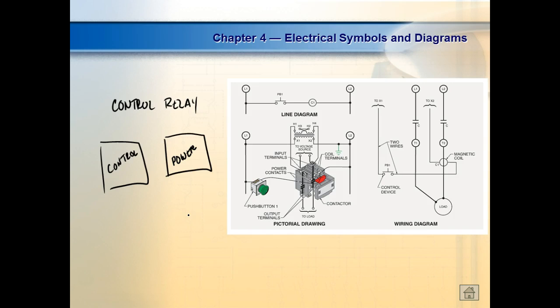So we have a control relay. A control relay, all its contacts are going to be in the what circuit? They're going to be in the control circuit. That's why we call it a control relay. A control relay's contacts never, ever leave the control circuit. Then we'll have another relay called a contactor. This guy could have contacts in the control circuit, but they're usually going to be what we call auxiliary contacts. And then they'll have their main power contacts over here.